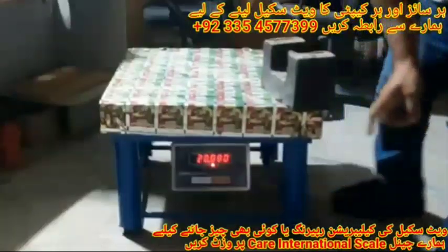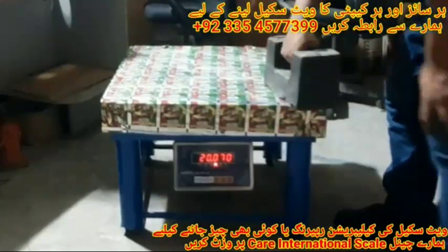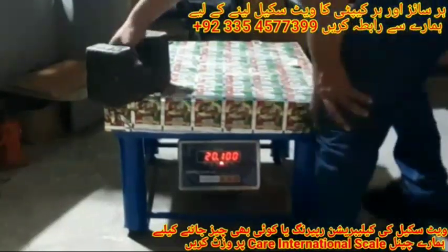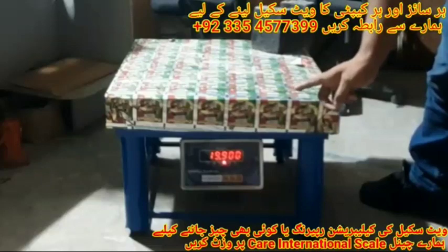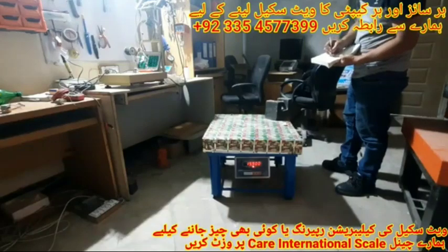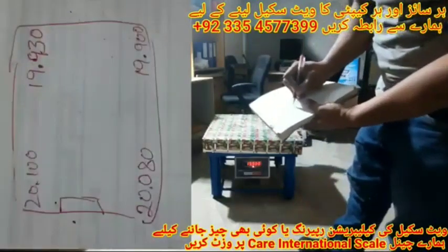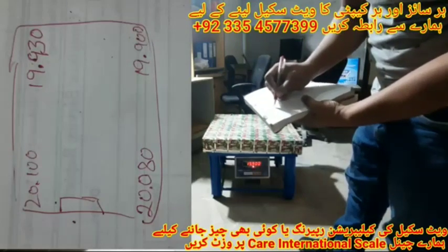Let's check the weight again. In the first corner it's now showing 20.080 grams, the second corner shows 20.100 grams, the third corner shows 19.900 grams, and the fourth corner shows 19.930 grams. In the diagram: first corner 20.080 grams, second corner 20.100 grams, third corner 19.900 grams, fourth corner 19.930 grams.